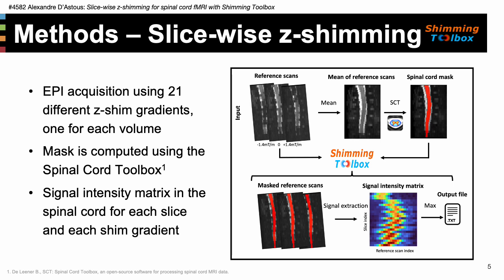This segmentation serves as the region of interest used for shimming. The z-shimming procedure consists in finding the z-shim gradient that maximizes the signal intensity in the spinal cord for each slice. To do so, a signal intensity matrix is calculated that includes information about each slice and each EPI volume. The maximum signal intensity of each slice in that matrix is used as the z-shim gradient for that slice. A text file is generated with the appropriate information and can then be used by the custom EPI sequence to perform slicewise z-shimming.